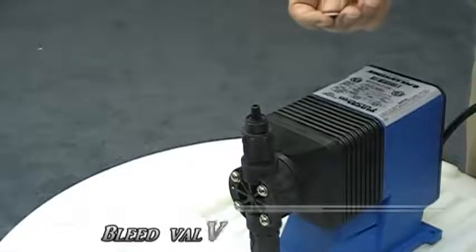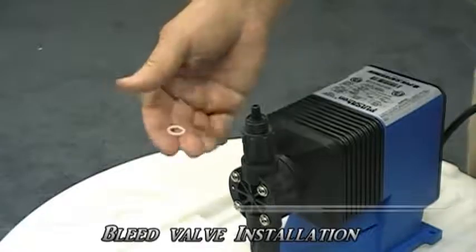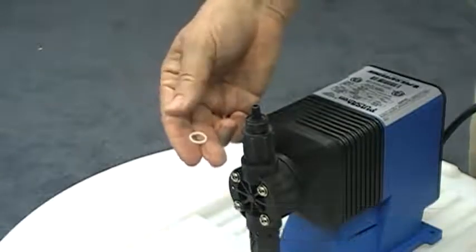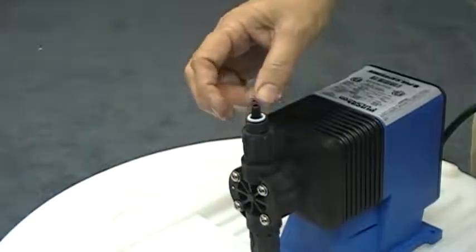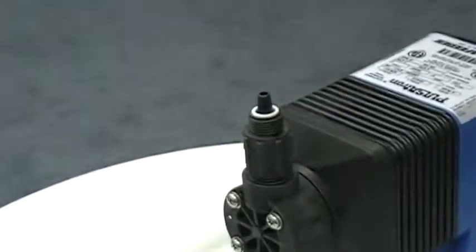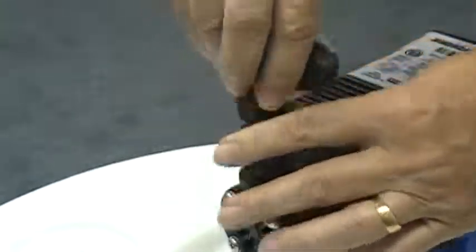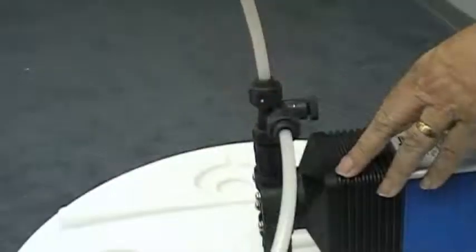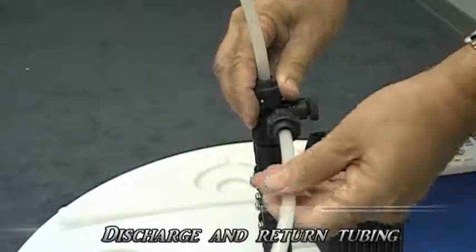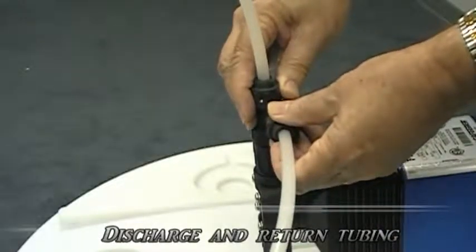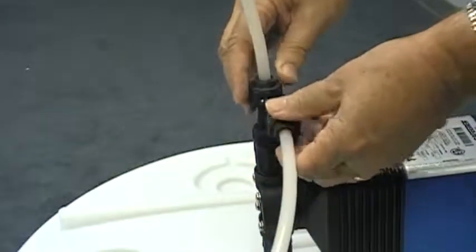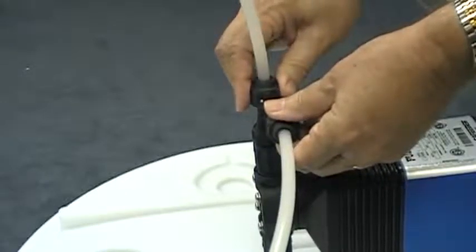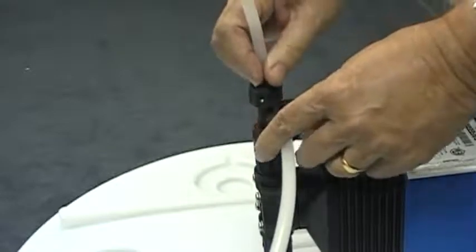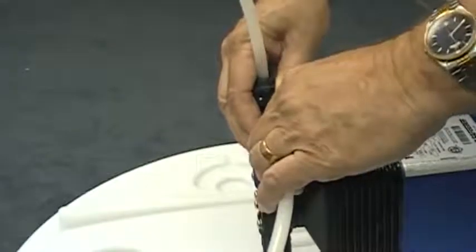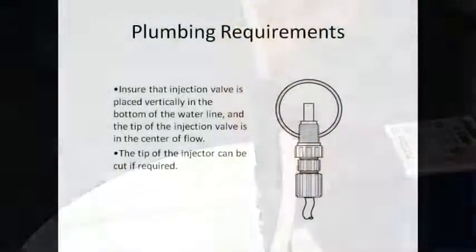The first step of installing the discharge tubing is to install the bleed valve. There is an O-ring in your accessory kit which is installed in the discharge valve groove. Then the bleed valve is attached to the top of the discharge valve. The discharge tubing is connected to the top of the bleed valve. The return tubing is connected to the side of the bleed valve and then placed in the top of the tank. All of these fittings are to be tightened hand tight. To make connecting the tube easier, they may be warmed prior to placing them on the compression fittings.